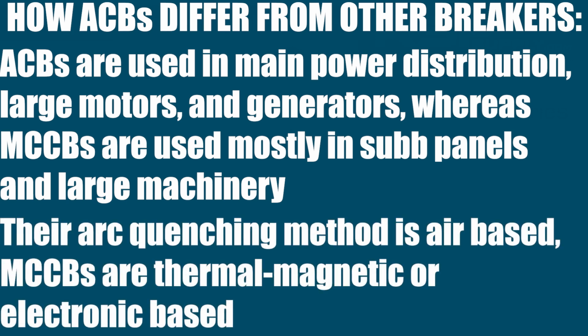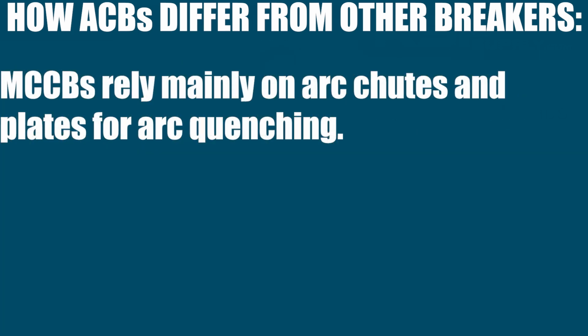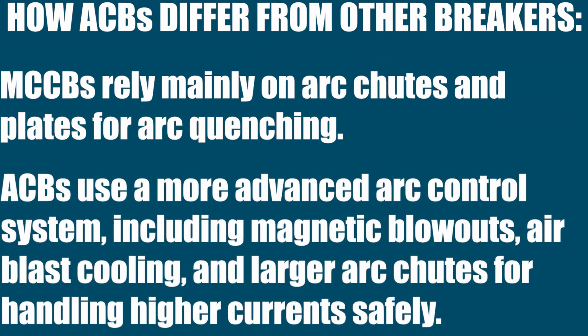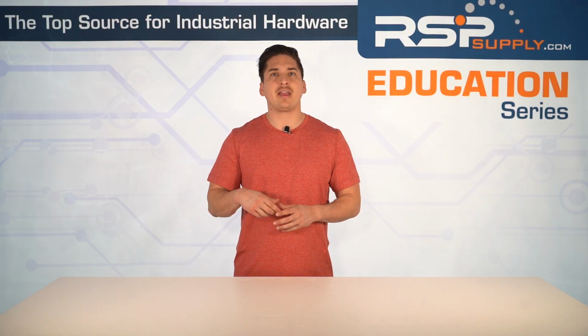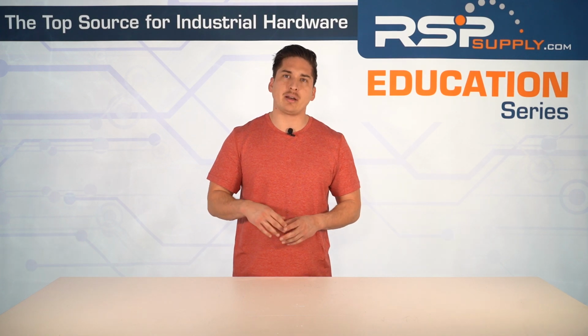Their arc quenching method is air-based. MCCBs are thermomagnetic or electronic-based. Molded case circuit breakers rely mainly on arc chutes and plates for arc quenching. Air circuit breakers use a more advanced arc controlling system, including magnetic blowouts, air blast cooling, and larger arc chutes for handling higher currents safely. A big pro of air circuit breakers is that they can be operated remotely. While molded case circuit breakers need to be operated manually, that's not the case with the ACB.